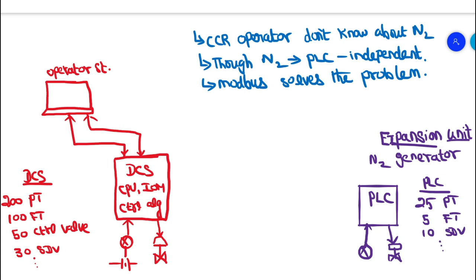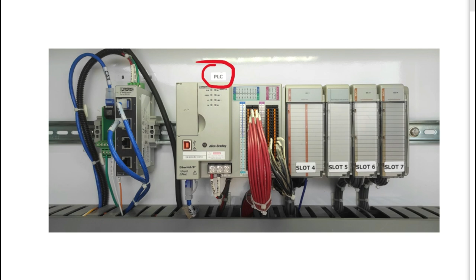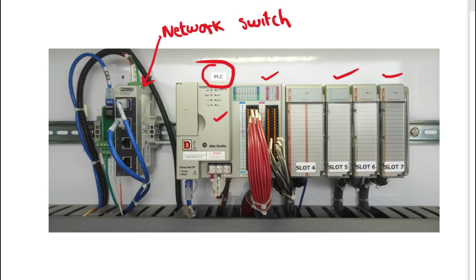So we just have to interconnect a Modbus cable between the PLC and the DCS, and this would be a single cable. For example, this is an Allen Bradley PLC. We have a CPU, input output modules, and a network switch, which acts as a hub to interconnect other control systems. This CPU gives data to the network switch, and from the network switch the cable is connected to the Modbus converter. It is an electronic component that converts this Ethernet data into Modbus communication.